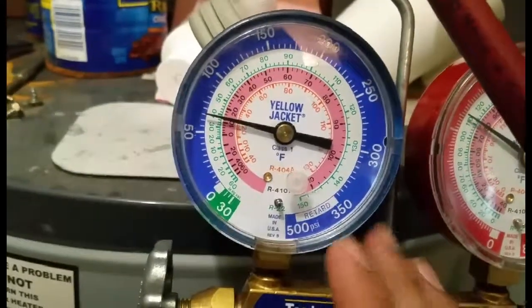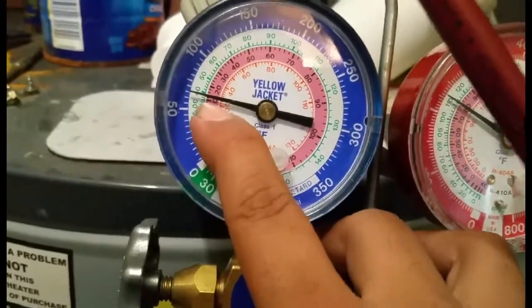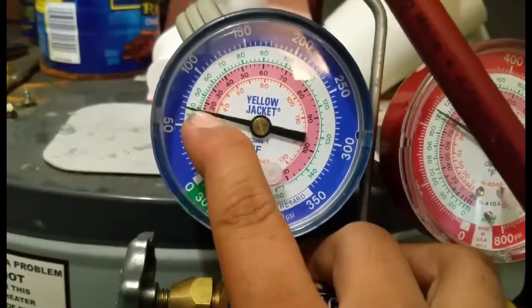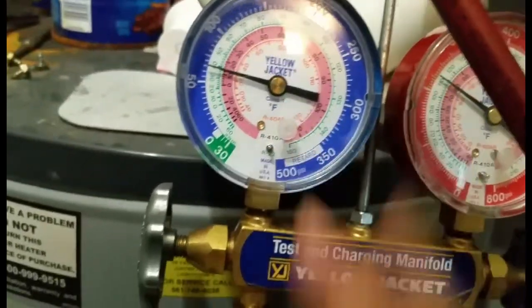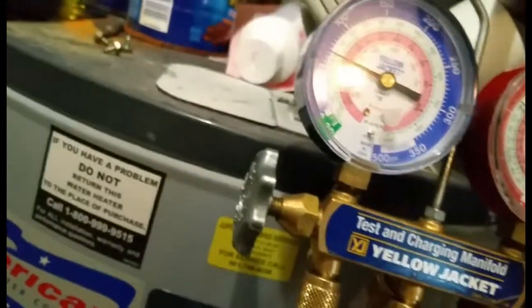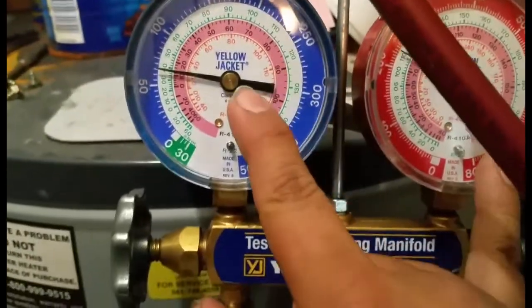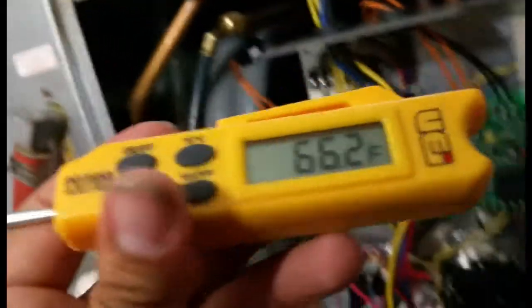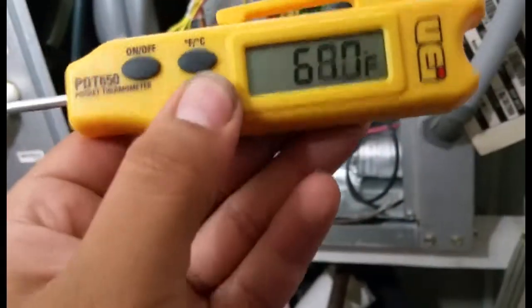Let's look at the pressures. Alright, it's 22. We got a 50. I'm gonna check the subcool and superheat in a little bit. But judging on the pressures, I usually use a different probe, but I left my other stab probe at my last customer's house. So 61.3. Let's see if that drops.